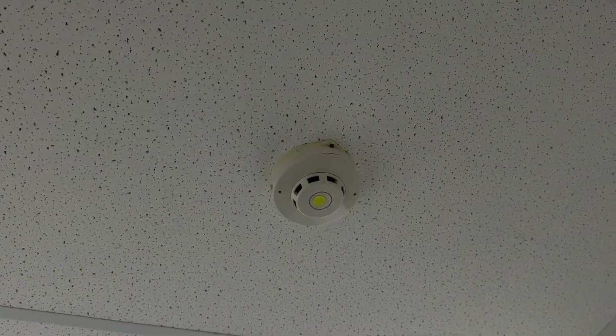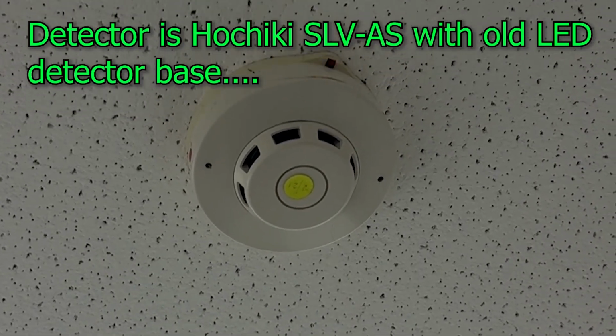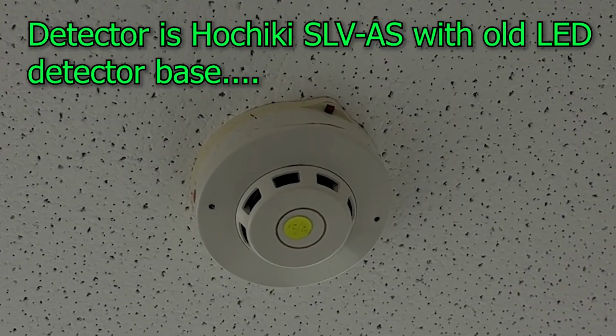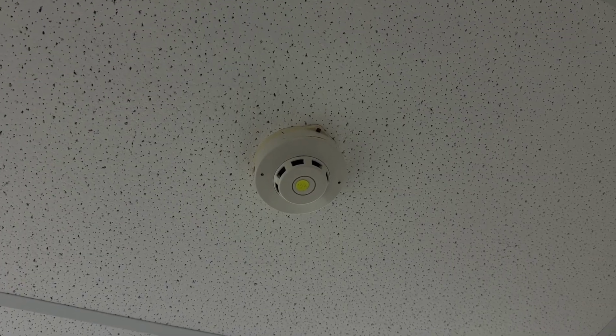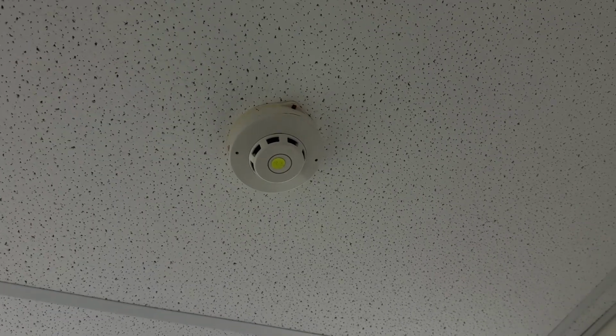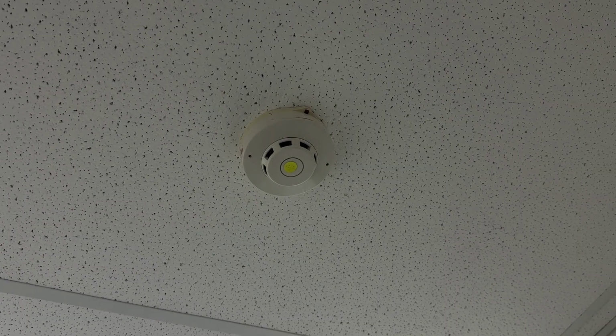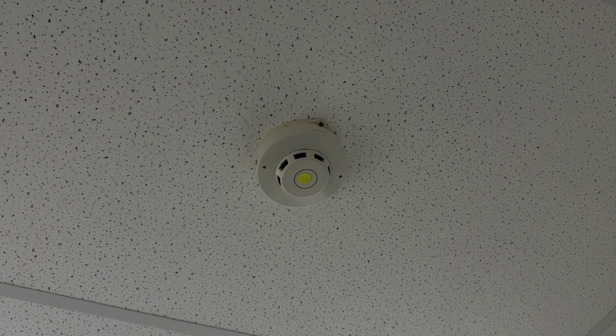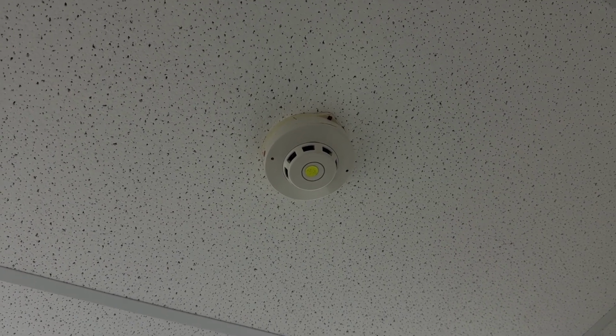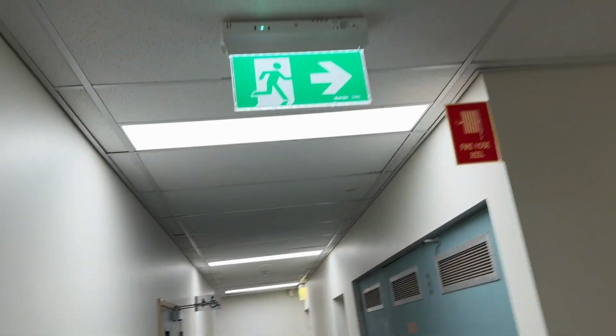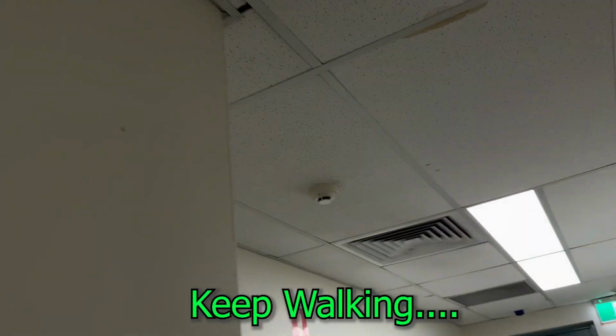If you notice, this detector is the old Hochiki with conventional base where the LED indicator is on. The old Hochiki SLV-AS doesn't have any indicator on the actual head of the detector. And that's a System Sensor 2151.